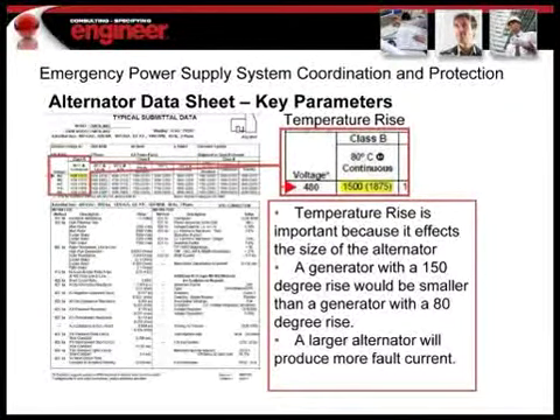What that does is affect the fault current that's available from that alternator. If you think about it in terms of the spinning alternator and the mass that is there, with the energy that is available when you have a fault, with a larger alternator, you're obviously going to have a lot more mass and a lot more spinning energy. When you have the fault, at that instantaneous moment, you can actually push a lot more fault out onto the bus. So it's important to note what temperature rise you're calling for, and keep in mind that it will affect the fault output.